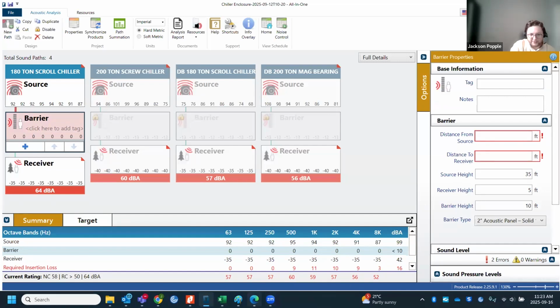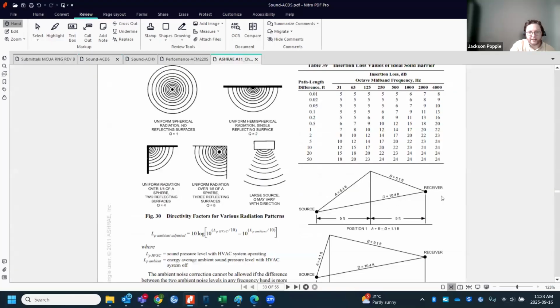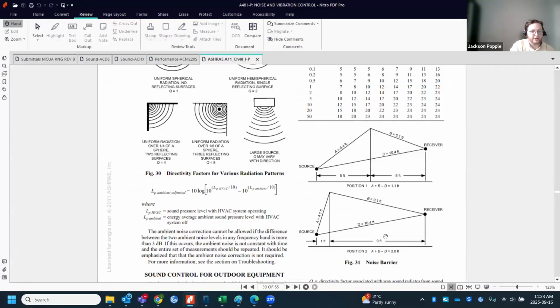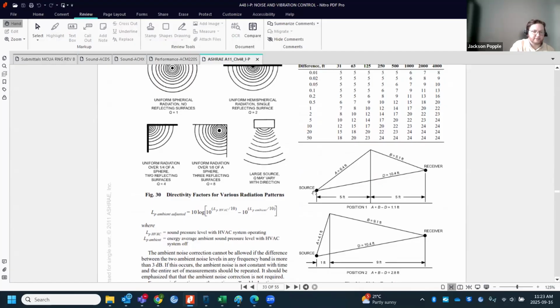I did do a little bit of a diagram. I'll also pull up this ASHRAE Applications Handbook—this is what we're looking at. Basically, we're trying to find the path length difference, which depends on how high the source is off the ground, how high the receiver is, how high the barrier wall is, and how far apart everything is. Based on that path length difference, which is just A plus B minus D—A being this distance, B this distance, D this distance—you get a set of insertion losses or transmission losses from your barrier. This is just the noise going over or around the barrier, not through it, but I'll show you a slightly different path afterward for noise through the barrier.